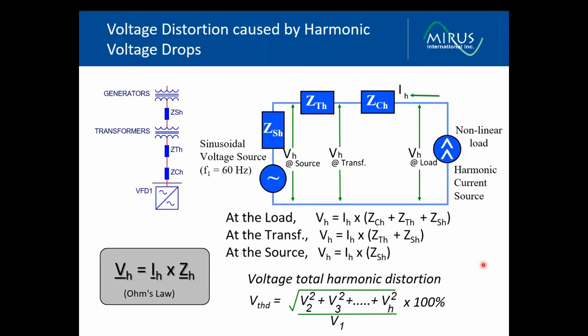And voltage distortion is the root sum square of all of the individual harmonic voltages divided by the fundamental component. So it's a measure of these voltage drops that are introduced as harmonic currents pass through the impedance of our power system.